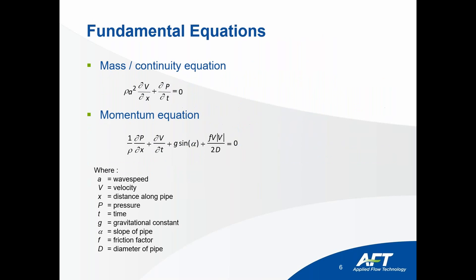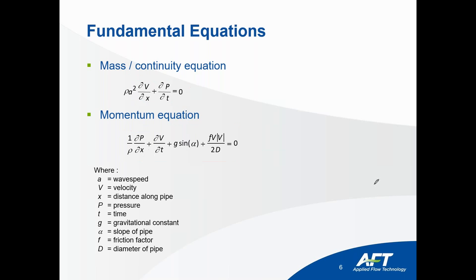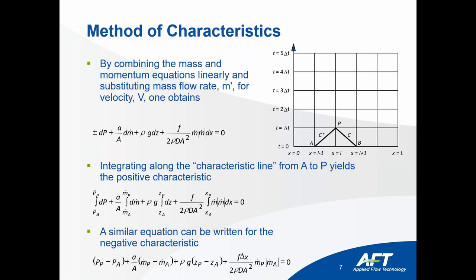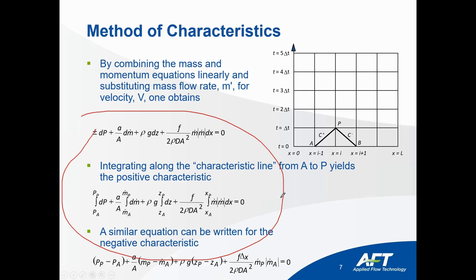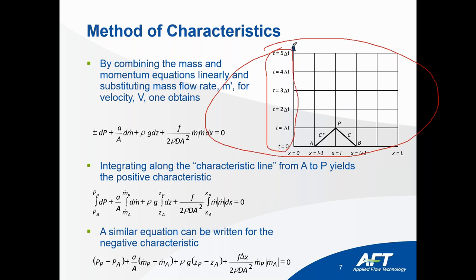Without going too much into the math, the key working equations for the transient that Impulse solves are the transient mass balance and the transient momentum balance. These are solved using the method of characteristics. The important thing to focus on is the method of characteristics grid — in order to do the transient calculations, you have to figure out the time step and break up your pipes into sections, or stations.